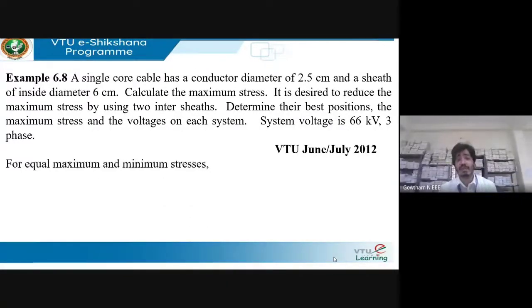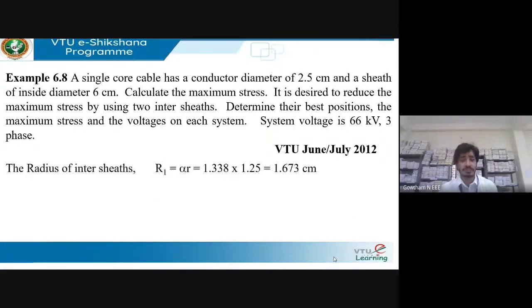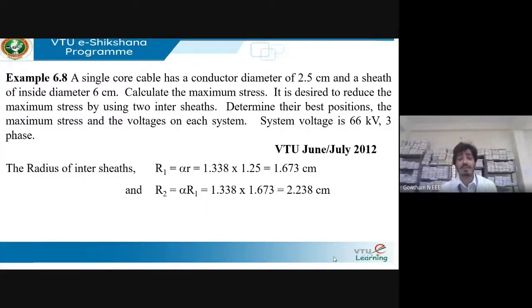For equal maximum stresses in all sections, set r1/r = r2/r1 = r3/r2 = α. Solving, α = 1.338. Radius of first inter-sheath: R1 = α × r = 1.338 × 1.25 = 1.673 cm. Radius of second inter-sheath: R2 = α × R1 = 2.238 cm.